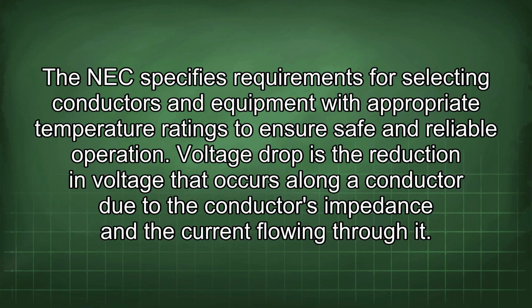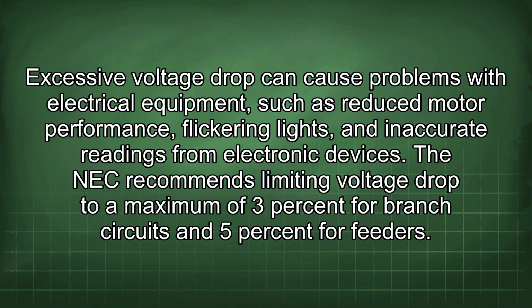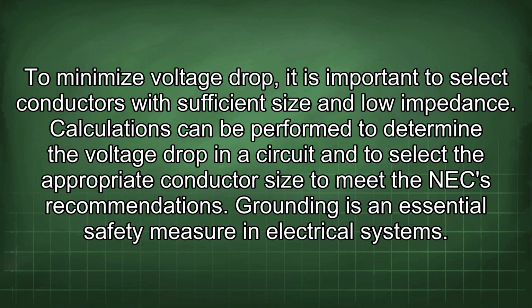Voltage drop is the reduction in voltage that occurs along a conductor due to the conductor's impedance and the current flowing through it. Excessive voltage drop can cause problems with electrical equipment, such as reduced motor performance, flickering lights, and inaccurate readings from electronic devices. The NEC recommends limiting voltage drop to a maximum of 3% for branch circuits and 5% for feeders. To minimize voltage drop, it is important to select conductors with sufficient size and low impedance.